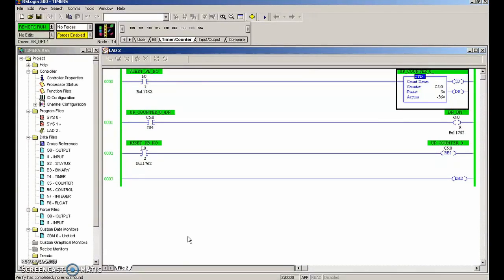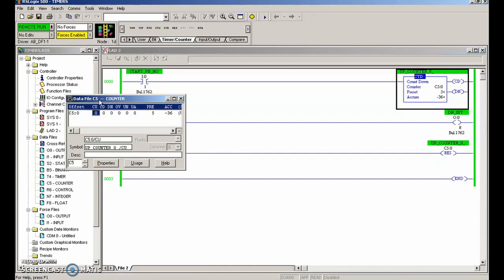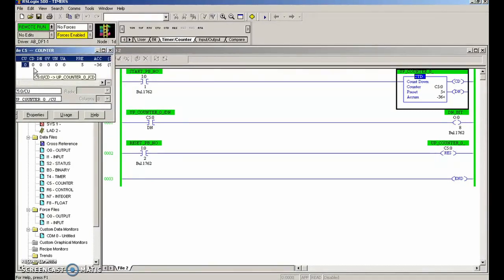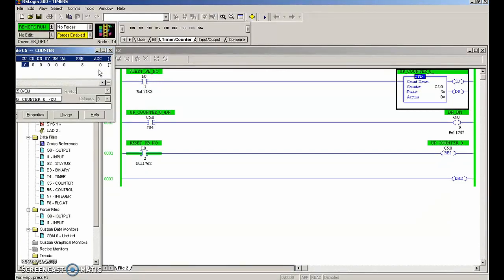The done bit never sets because that value is nowhere near five. Let's hit our reset push button - the accumulated value goes right to zero. We can see on the counter instruction that every time I hit that push button it goes to a one, and the accumulated value goes down: minus six, minus seven, minus eight, minus nine. When I hit reset, the accumulated value goes back up to zero. Now we've got an up counter and a down counter.